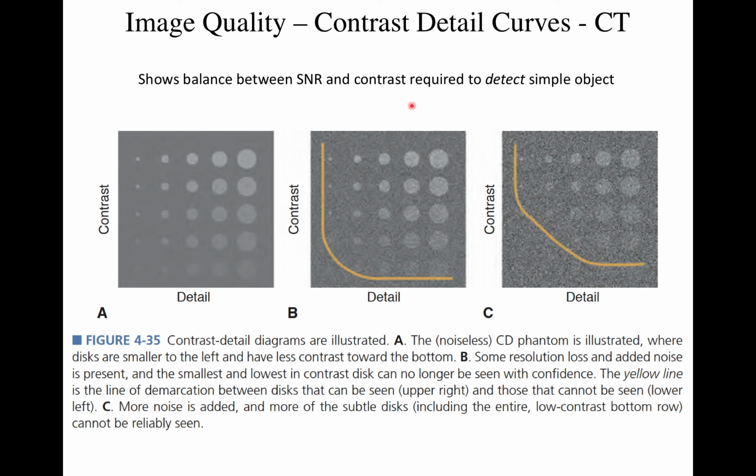So this is called a contrast detail curve, which gives you a quick summary, when you look at the picture, of what you can resolve at a given signal to noise, right? And it is organized as follows. Higher spatial frequencies are over here. They're smaller dots, okay? And for a specific spatial frequency or diameter of my disk, you look at different contrasts, and these are like percent contrast. So this could be 10%, this could be 1% change.